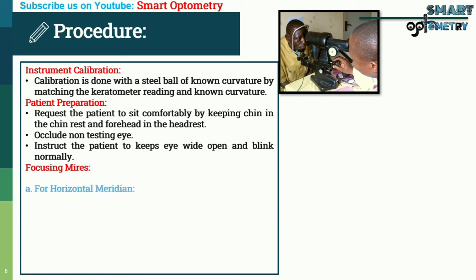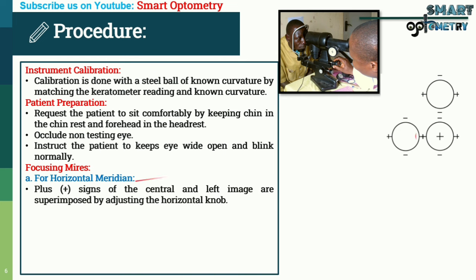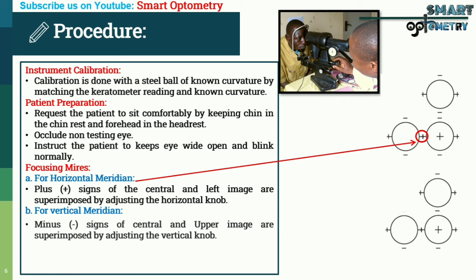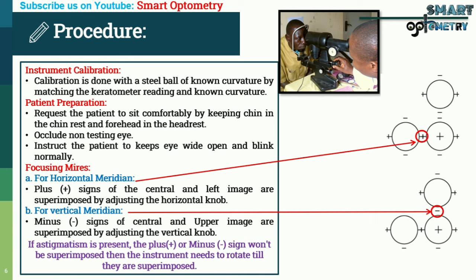Focusing mires: for the horizontal meridian, the plus sign of the central and left image are superimposed by adjusting the horizontal knob. For the vertical meridian, the minus sign of the central and upper image are superimposed by adjusting the vertical knob. If astigmatism is present, the plus and minus signs won't be superimposed, and the instrument needs to be rotated until they are superimposed.